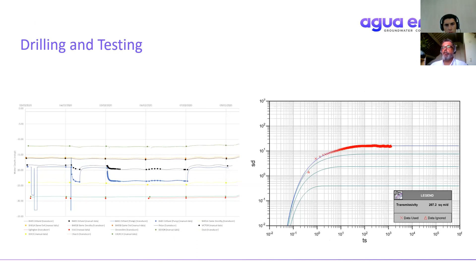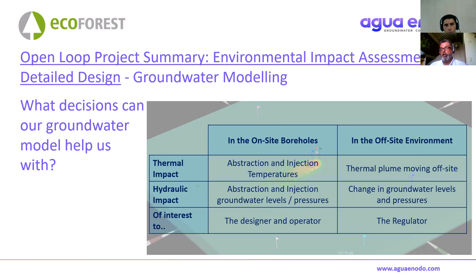I'll skip through this quickly, but as touched on earlier, our two main areas of interest are thermal and hydraulic impact. Thermal impact is about what happens to the warmer or colder water once it's gone into the ground—does it return to your abstraction borehole, or migrate off-site, perhaps to a wetland we don't want to warm up? Hydraulic impact is whether you're lowering or raising groundwater levels to an unacceptable elevation.